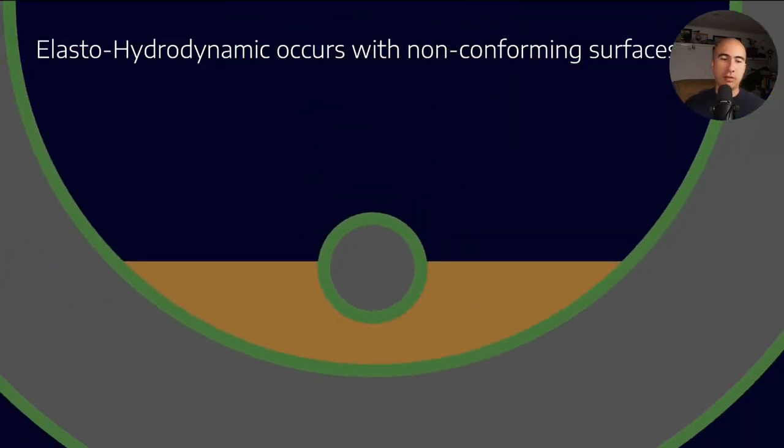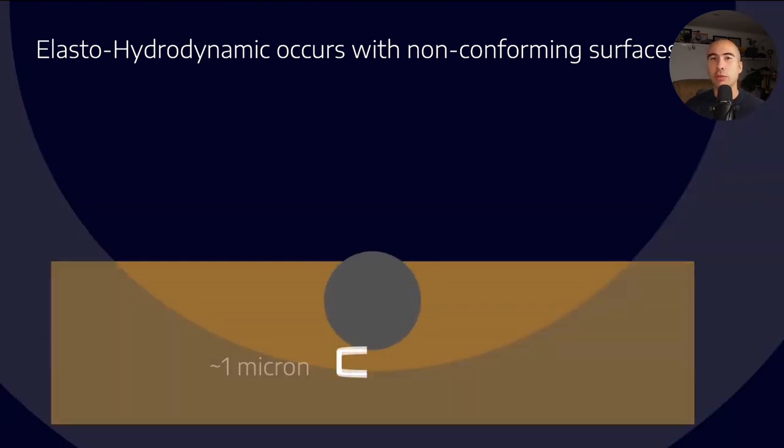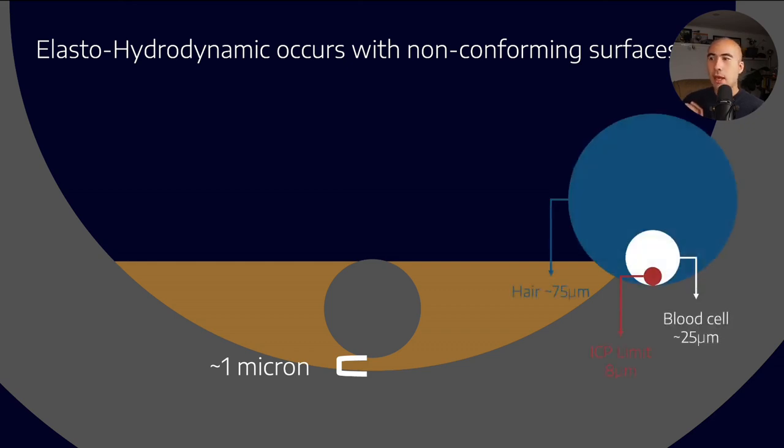With elasto-hydrodynamic lubrication, we have a substantially thinner lubricant film. Rather than 50 to 200 microns, we're talking single-digit microns. To give you an idea, a white blood cell is 25 microns, invisible to the naked eye. The ICP detection limit for oil analysis is about 8 microns.